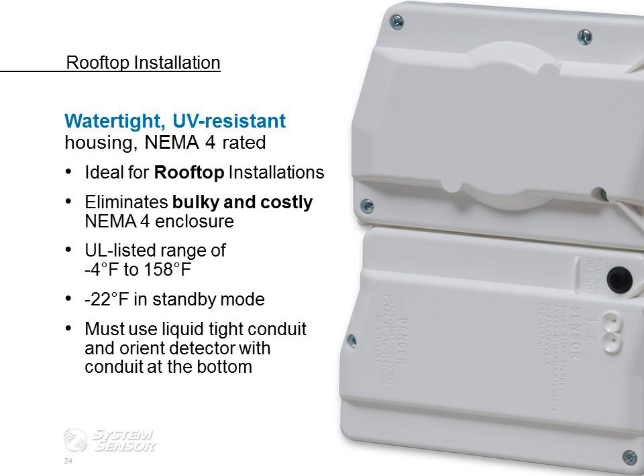Another thing that we'll see in rooftop installations, if it's not a factory installed and we're going back into a field installed application or service replacement work, that type of thing, we can also use our watertight UV resistant housing, our NEMA 4 rated product. It's great for rooftop installations. It eliminates the bulky and costly NEMA 4 third party enclosure. It's UL listed. Temperature range is -4 to 158 degrees Fahrenheit. It's listed down to -22 degrees Fahrenheit in standby mode.